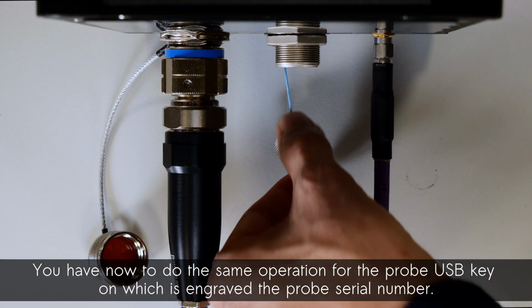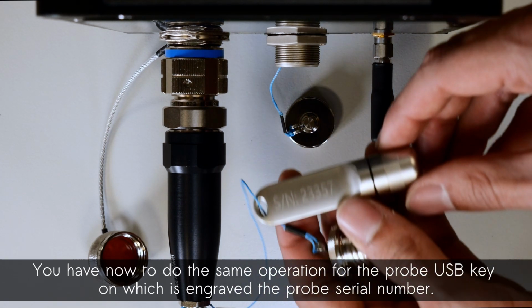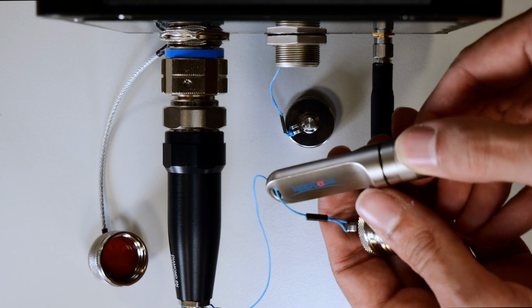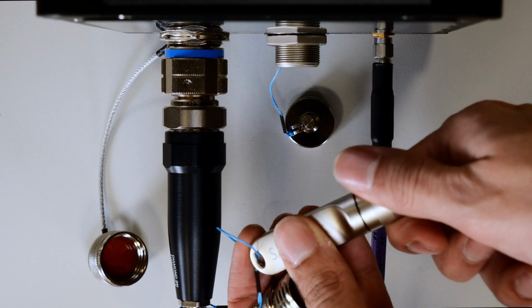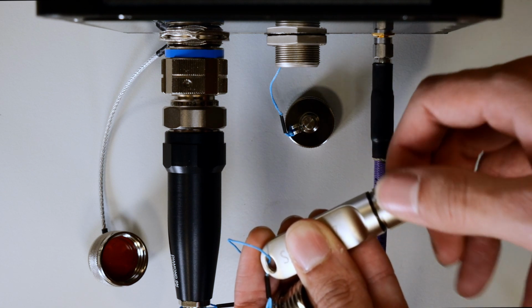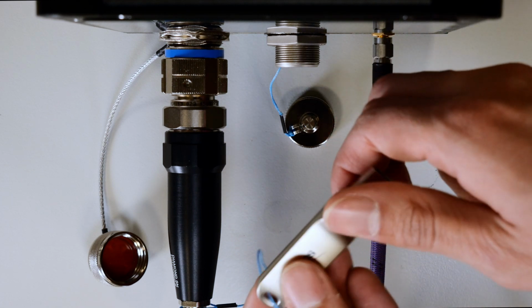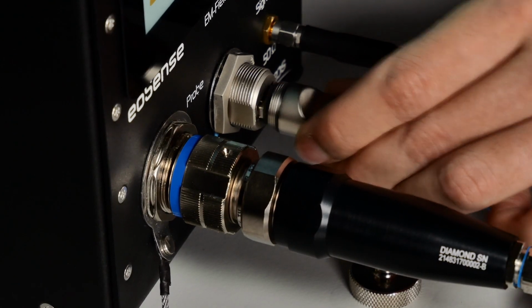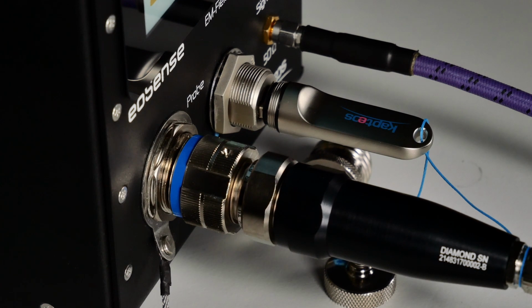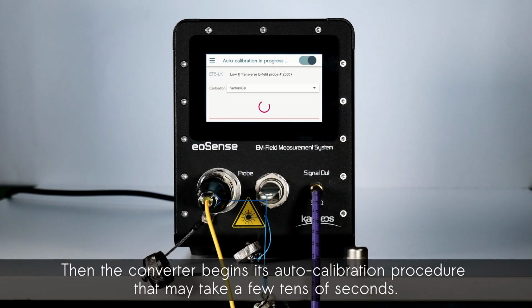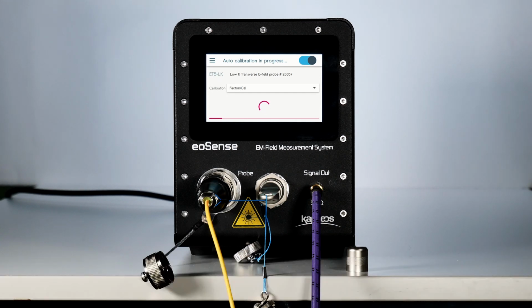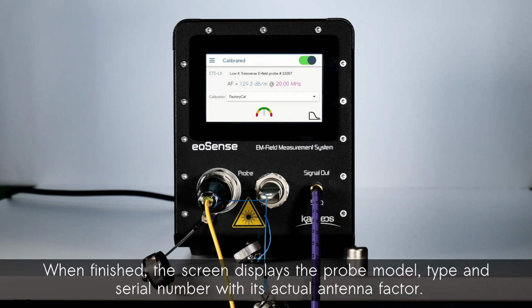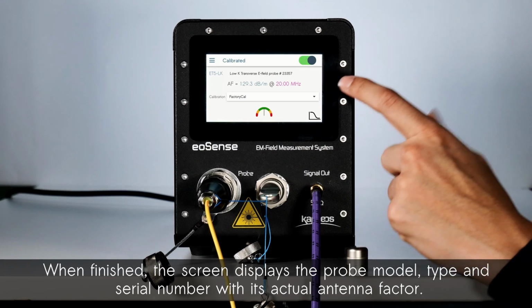You have now to do the same operation for the probe USB key on which is engraved the probe serial number. Then the converter begins its auto-calibration procedure that may take a few tens of seconds. When finished, the screen displays the probe model, type and serial number with its actual antenna factor.